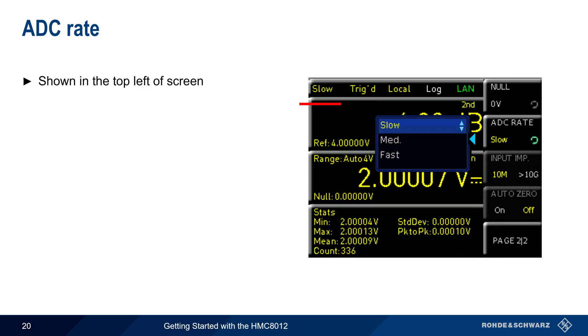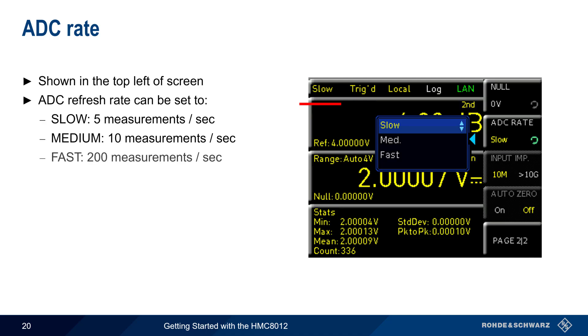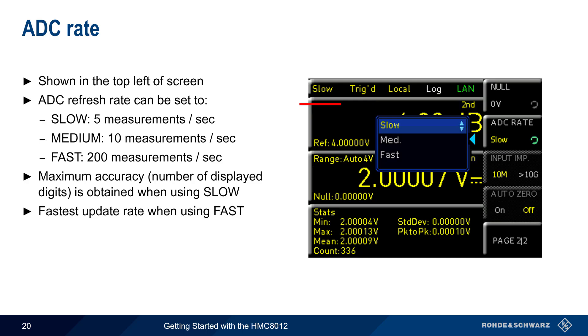The rate of the HMC's analog-to-digital converter is shown in the top left corner of the screen. There are three settings for ADC rate: Slow has a measurement rate of 5 measurements per second, Medium has a rate of 10 measurements per second, and Fast produces 200 measurements per second. The maximum measurement accuracy, or highest number of displayed digits, is obtained when using the slow ADC rate, while the fastest measurement update rate occurs when ADC rate is set to fast.